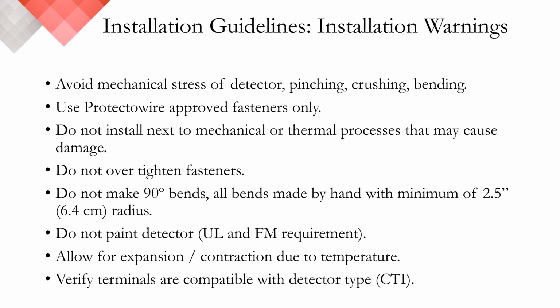Like our guidelines for storage of your device, we also have a few areas to pay close attention to while installing your detector. First, you want to avoid any mechanical stress of the detector. The support should not pinch or crush. Be sure to use only Protectowire-approved fasteners. Do not make or induce any 90-degree bends when installing. All bends should be made by hand and not exceed the minimum 2.5 bend radius. Do not paint the detector. Doing so will void your listing.